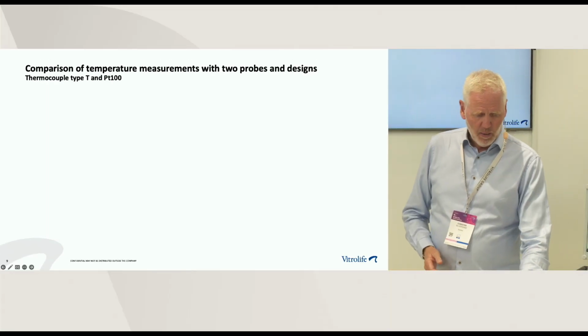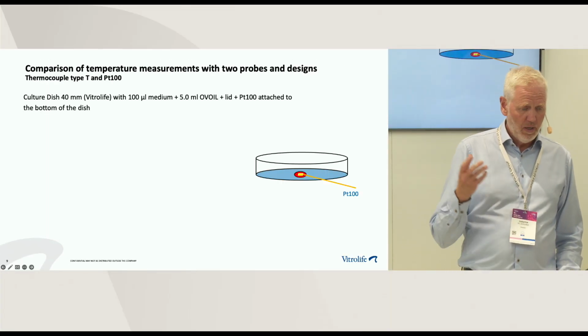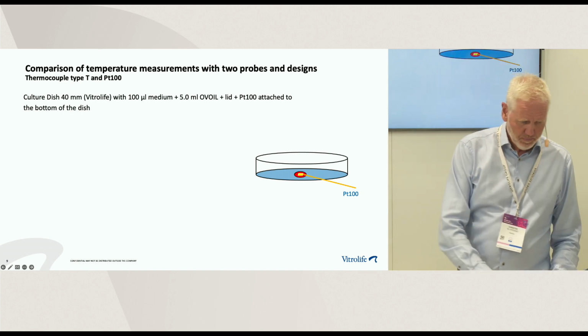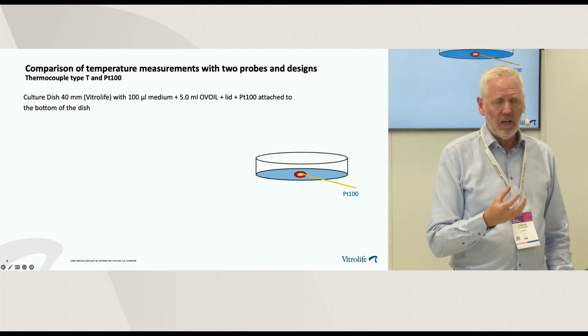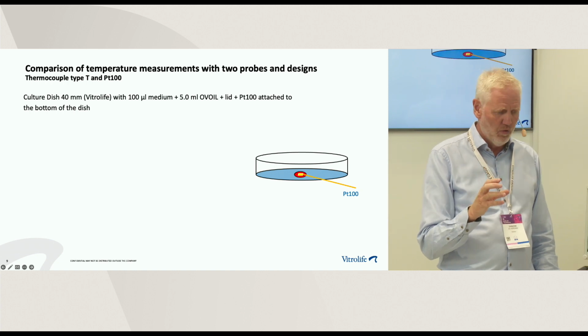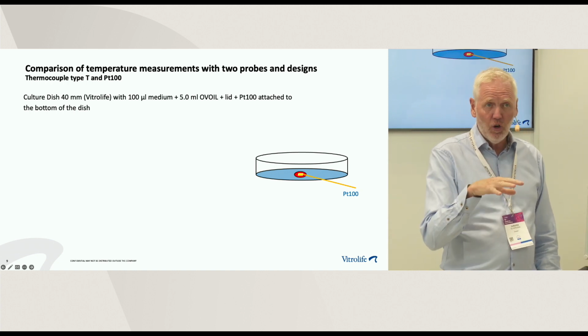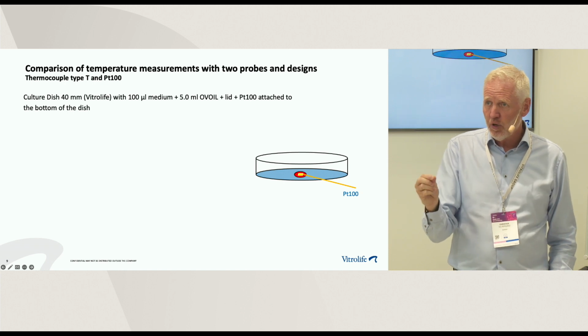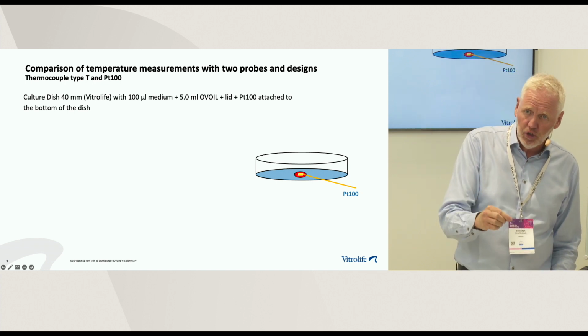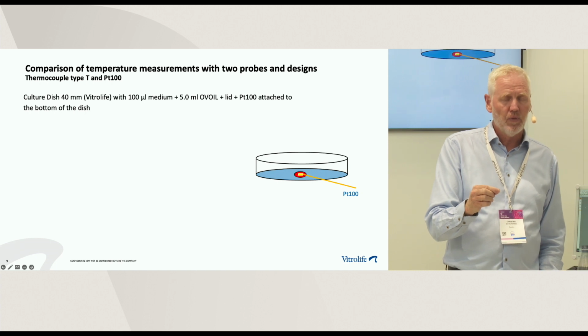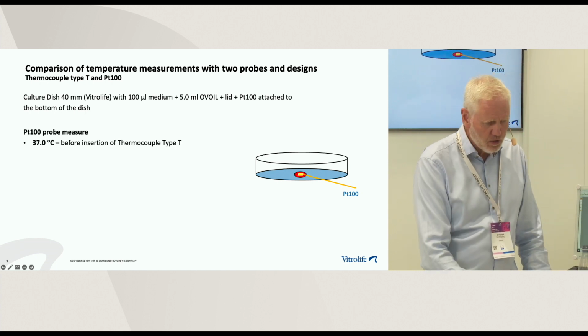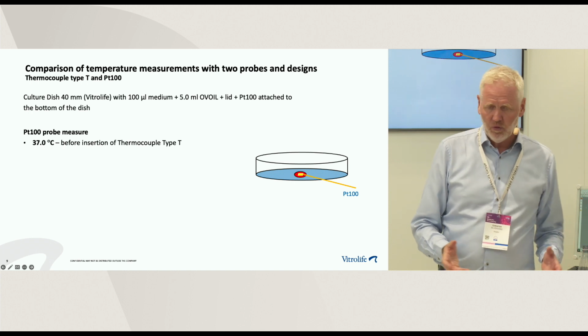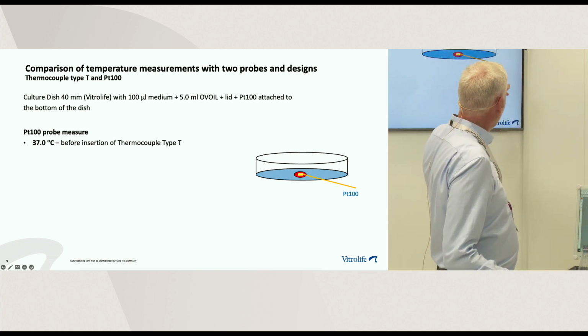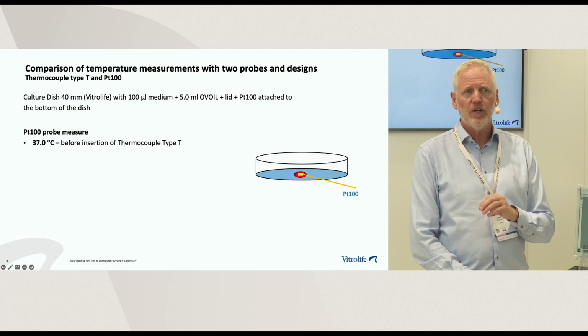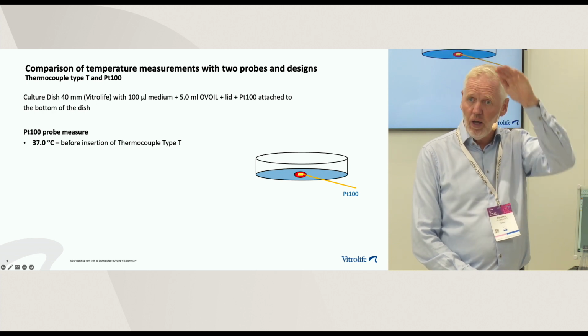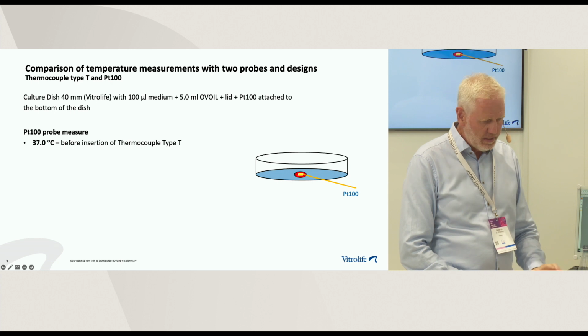I'm now comparing them. So I have a culture dish, a 40 millimeter dish, drawn here. We have 100 microliter medium. We have 5 milliliter oil. We have the lid on. We have a PT100 attached to the bottom, and we're then going to insert a thermocouple type T probe. So this is what happened. The system is now set. So measuring the temperature with the PT100 probe, we have 37 degrees in the microdroplet, under the oil, under the lid. This is the setting.